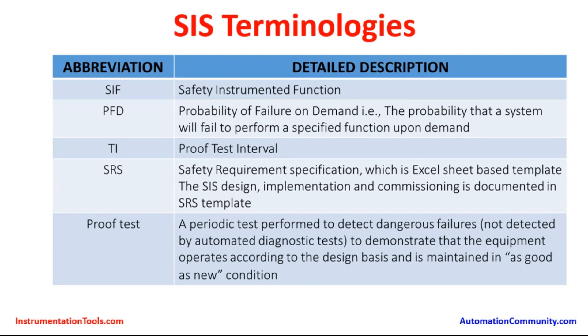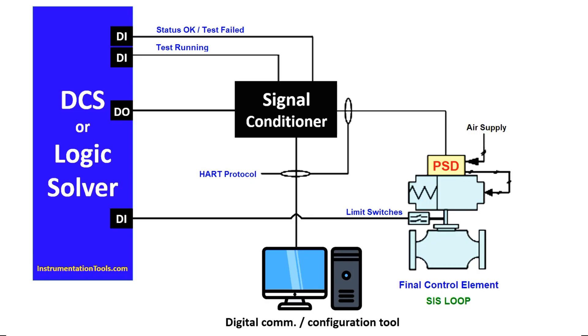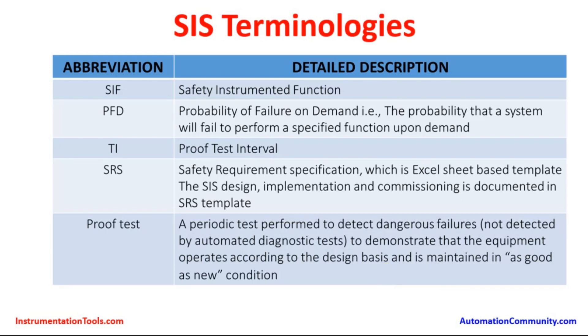Whoever will be working on SIS design has to understand and fill up the Safety Requirement Specification before going into the process implementation. Proof Test is a periodic test performed to detect dangerous failures which are not detected by automatic diagnostic tests, to demonstrate that the equipment operates according to the design basis and is maintained in as-good-as-new condition. A proof test is performed for the SIS sensors, logic solvers, and final elements.